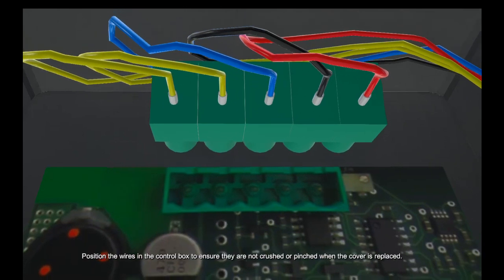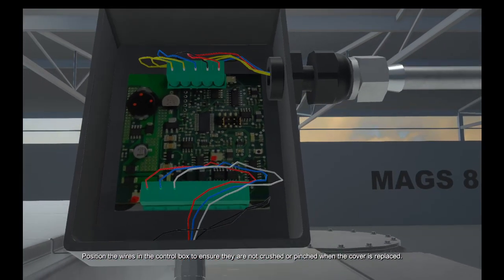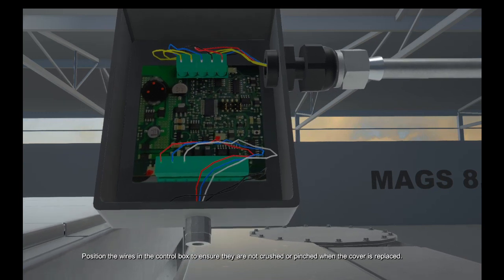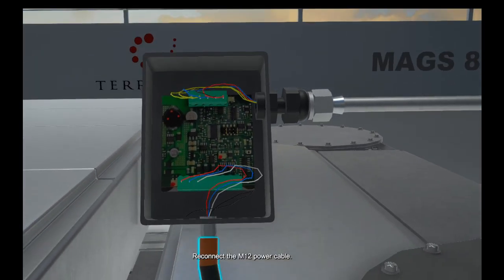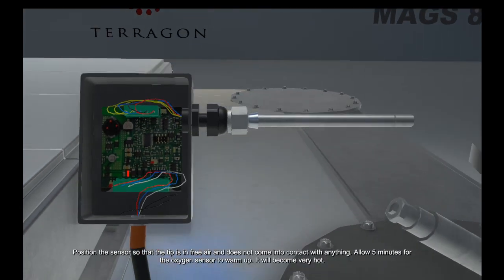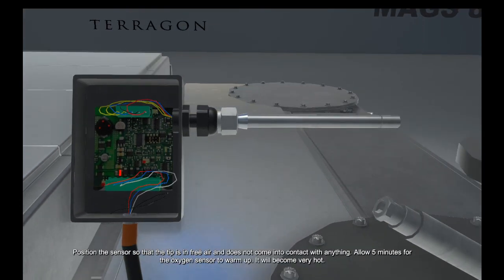Position the wires in the control box to ensure they are not crushed or pinched when the cover is replaced. Reconnect the M12 power cable. Position the sensor so the tip is in free air and does not come into contact with anything. Allow 5 minutes for the oxygen sensor to warm up. It will become very hot.